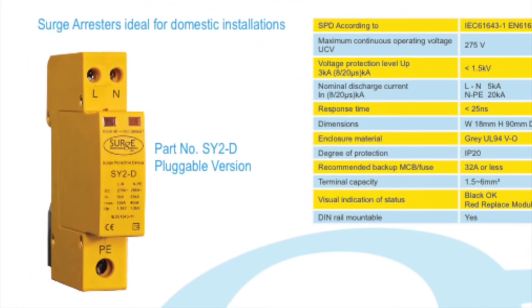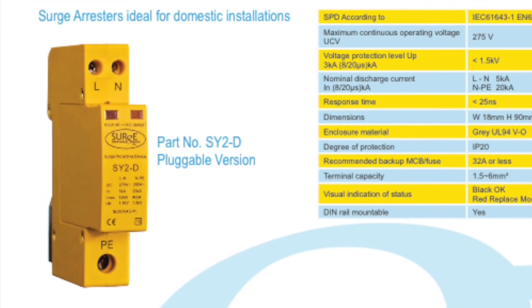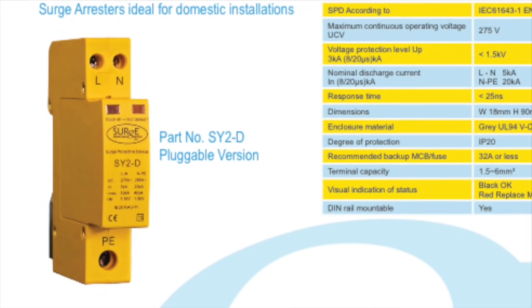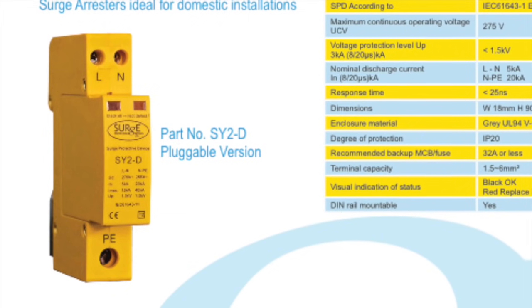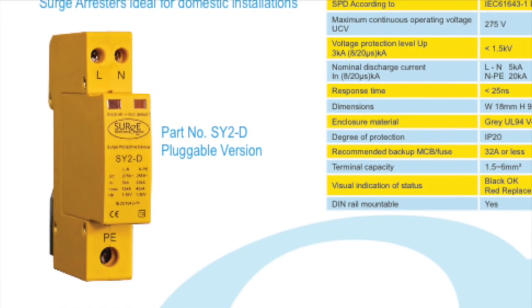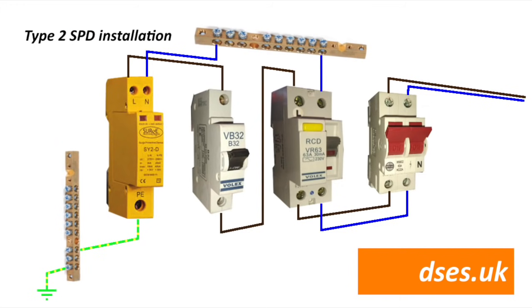However, notice that the bottom terminal is for protective earth. This model does not sit on the busbar, so in retrofit applications the busbar may need to be cut down. As shown here in my somewhat perspectively challenged picture, knocked out after one whiskey too many I fear, the protective earth terminal is shown connecting to the MET in the consumer unit while the line connects to a 16 to 32 amp breaker.